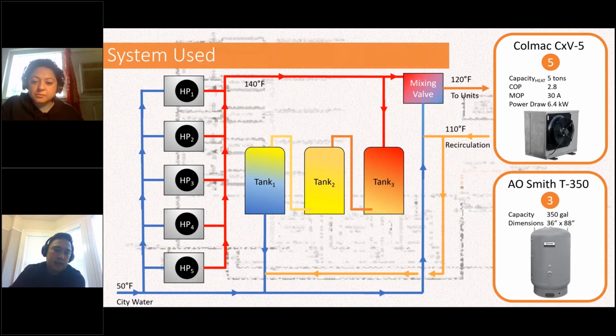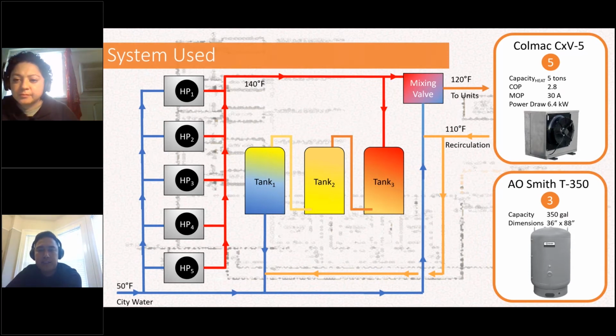So the way it works is the city water at the bottom left corner of the screen comes in and goes into our heat pumps, which are lined up in parallel. The water's heated up to 140 degrees and kind of bifurcates into the storage tanks, which are set up in series, and into the mixing valve. The mixing valve cools down the water to 120 and out to the units. We also anticipated a 10-degree drop in the recirculation, which would eventually end up back into the system and recycle all over again.